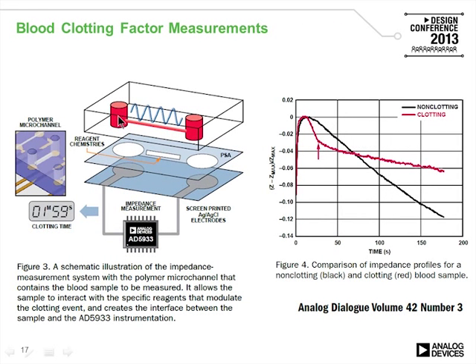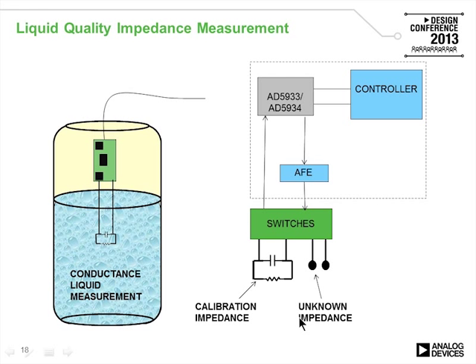A blood sample is smeared on a slide and impedance is measured as a function of time. For healthy blood, impedance drops and then levels off as clotting occurs. For blood that does not clot properly, impedance continues to change—shown as the black curve. This was documented in an Analog Dialogue article. For liquid conductance or impedance measurements, probes are immersed in the liquid to measure both resistance and capacitive effects from metallic content. CMOS switches can select between calibration and unknown impedance.